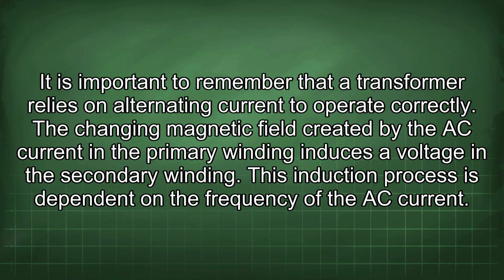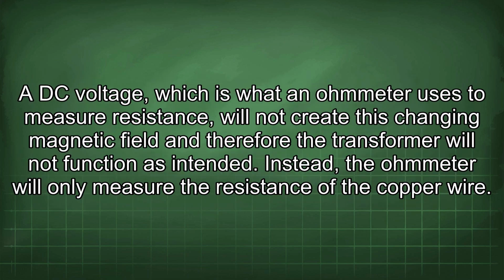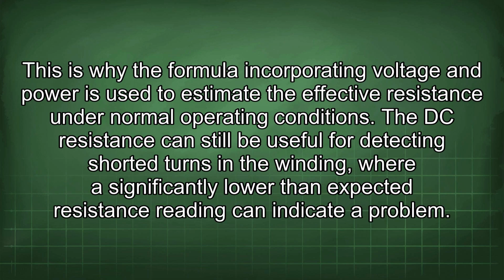It is important to remember that a transformer relies on alternating current to operate correctly. The changing magnetic field created by the AC current in the primary winding induces a voltage in the secondary winding. This induction process is dependent on the frequency of the AC current. A DC voltage, which is what an ohmmeter uses to measure resistance, will not create this changing magnetic field, and therefore the transformer will not function as intended. Instead, the ohmmeter will only measure the resistance of the copper wire. This is why the formula incorporating voltage and power is used to estimate the effective resistance under normal operating conditions.